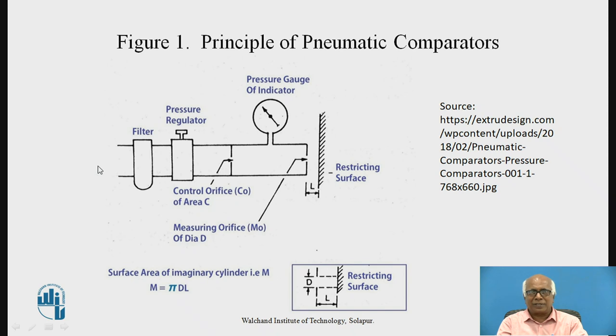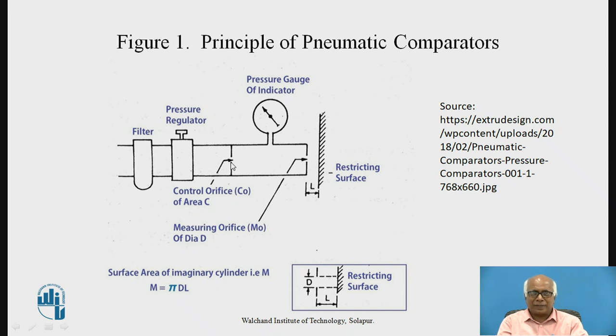Compressed air comes through the filter. There is a pressure regulator unit — filter and pressure regulator units are common for any pneumatic system. There is a control orifice, named CO with area C. This is a chamber whose pressure can be measured with the pneumatic gauge. There is one more orifice — the measuring orifice — through which the measuring jet emerges and air goes to the atmosphere. The distance between the restricting surface and the measuring orifice MO is designated by L.